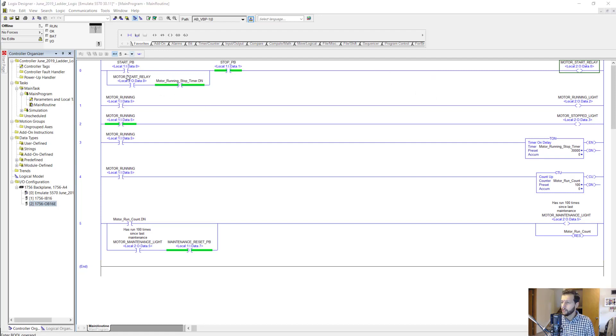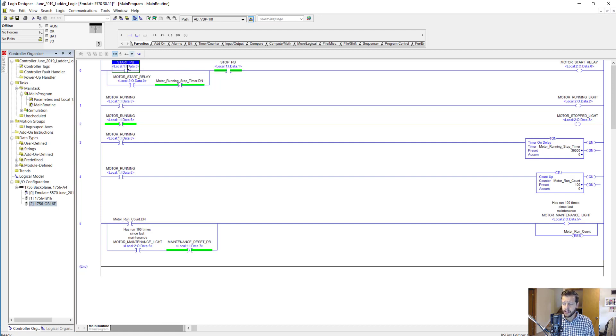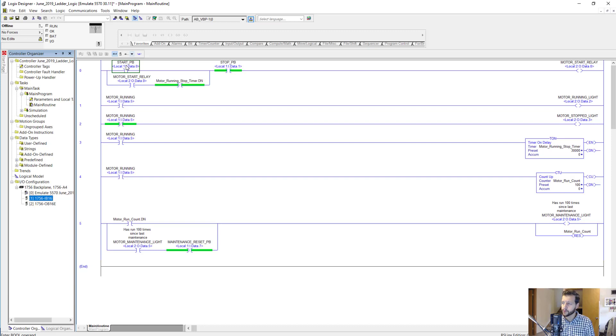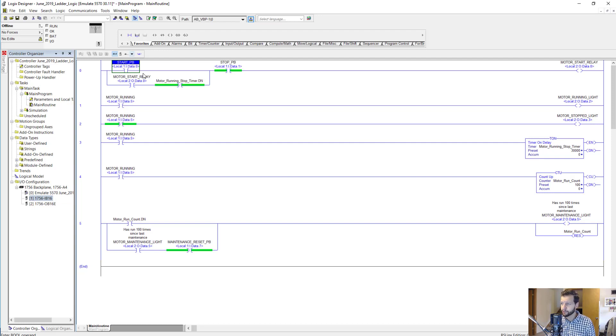Notice how the start PB—PB stands for push button—has an address underneath the actual tag name. Start PB is the tag name and then we have this address under here, and this is called an alias. Basically it addresses one of the points from this input module. The syntax says local, so that means the local rack, which would be the same rack that the controller is in. Then we have one, which would be slot one.